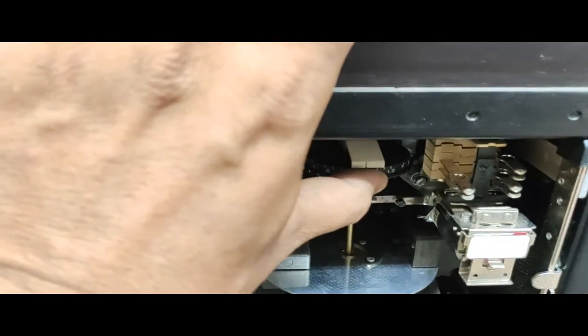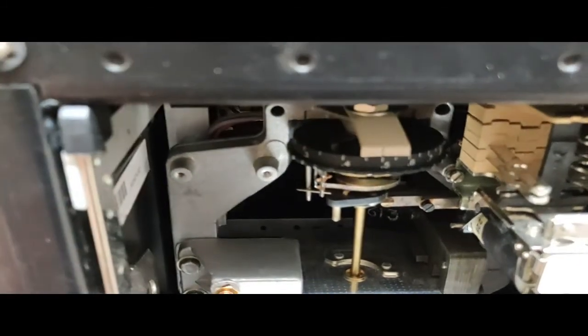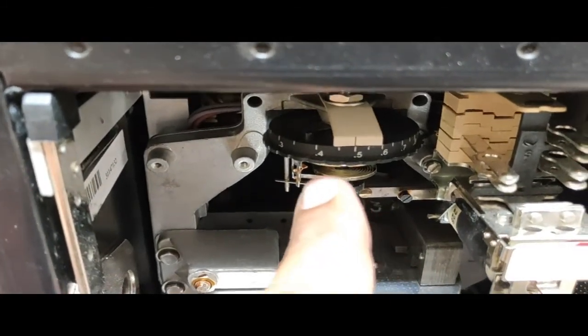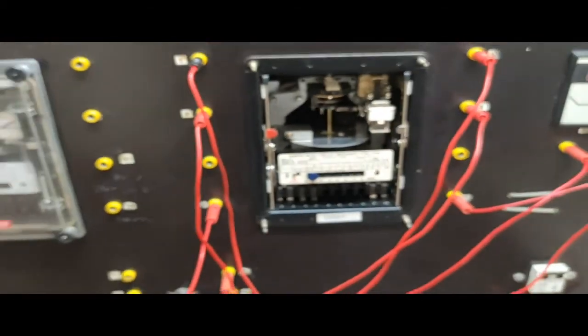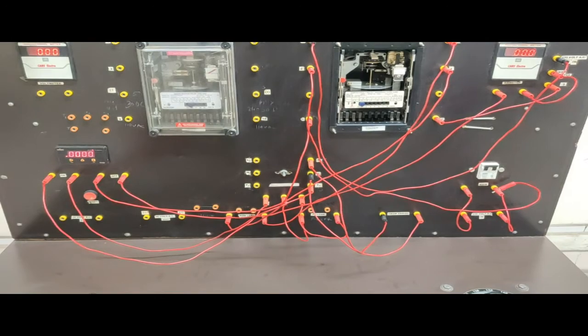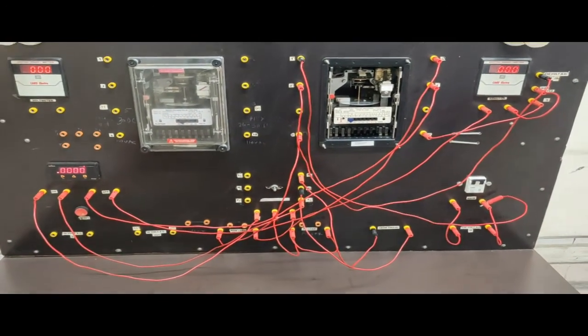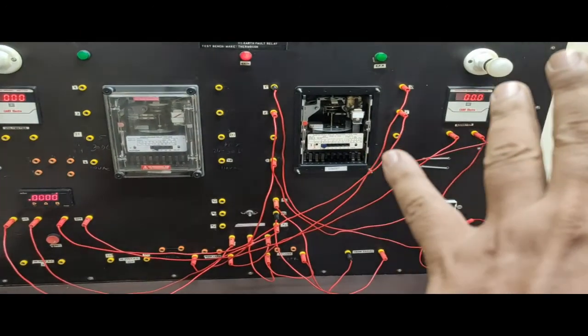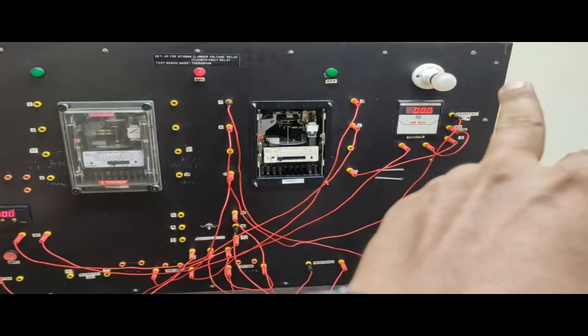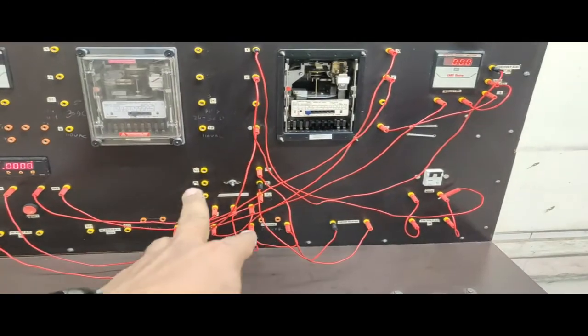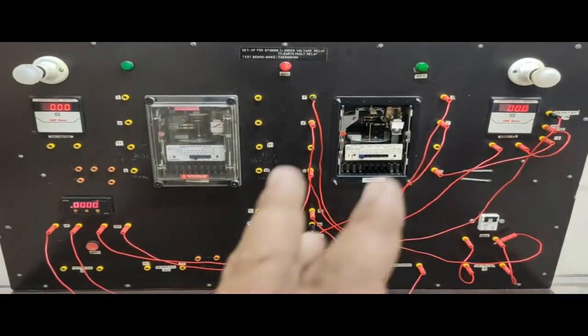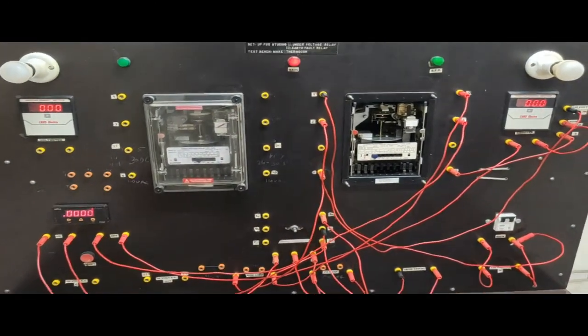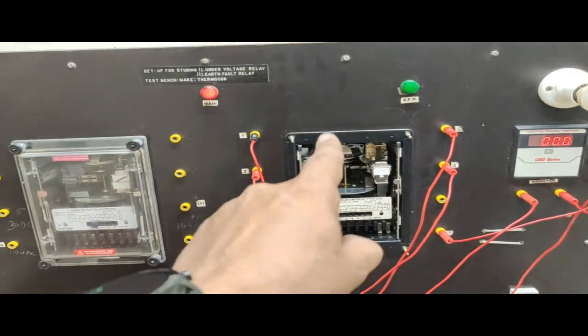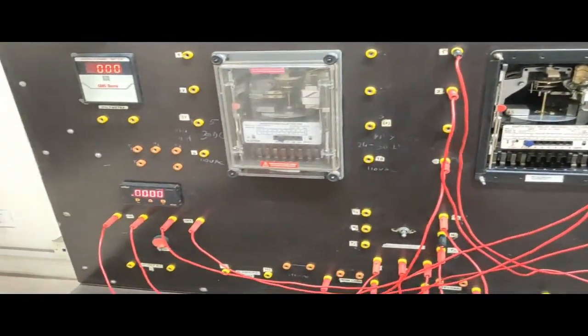Now let's see how to change the relay operating time. So I now move the time setting multiplier to set it at 0.5. So here you see now it is set at 0.5. Okay, 0.5. So obviously the relay will take less time to operate. Okay, same settings are there. So that means the relay coil current is 0.8 ampere if I just put the switch in the downward position. So everything will be the same. The plug setting multiplier will be 4. But now I just change the time setting multiplier from 1.0 to 0.5. Now let's see how much time is required.